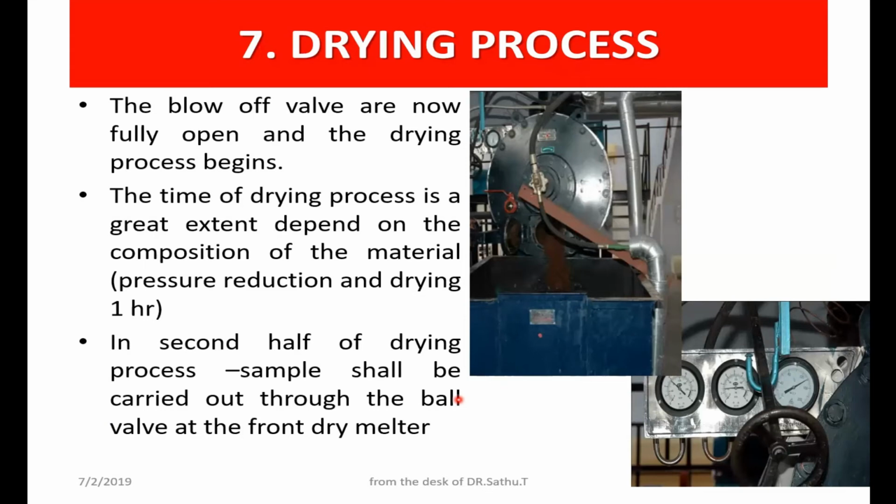Here the blow off valve is now opened. Slowly we open the blow off valve during the pressure reduction, and ultimately we completely open the blow off valve, and the drying process begins. During the drying process also, we send steam inside the jackets. Only then, out of that heat, the moisture will be evaporated from the raw material. The time for the drying process greatly depends upon the composition of the material, what type of raw materials you use, so we have to standardize.